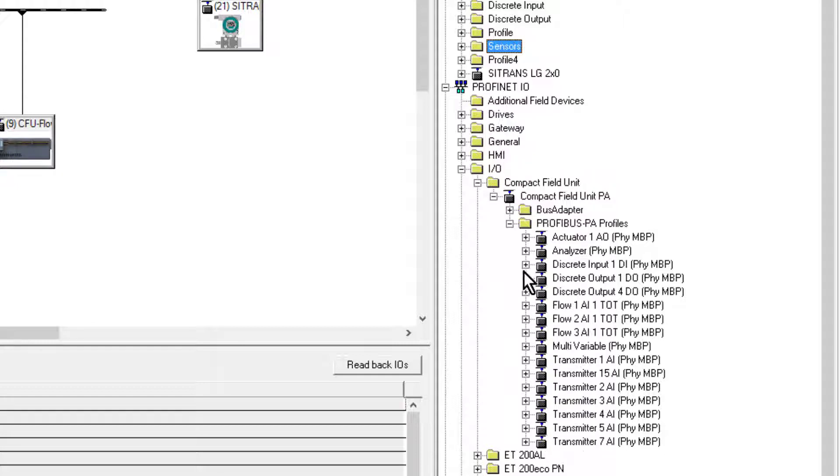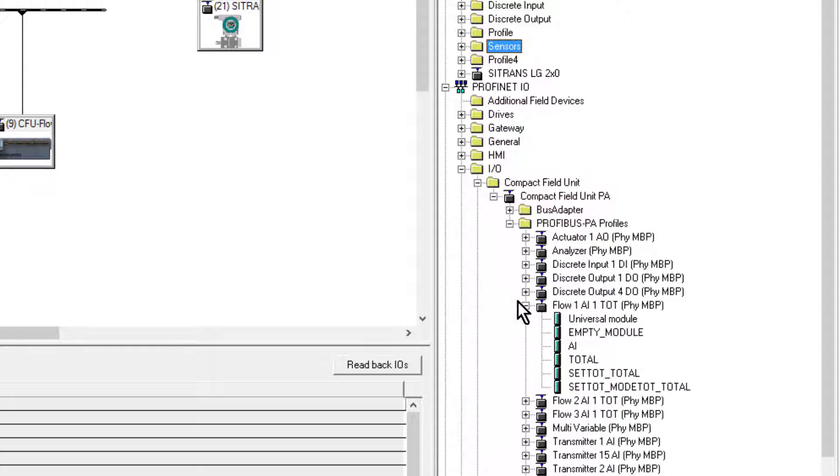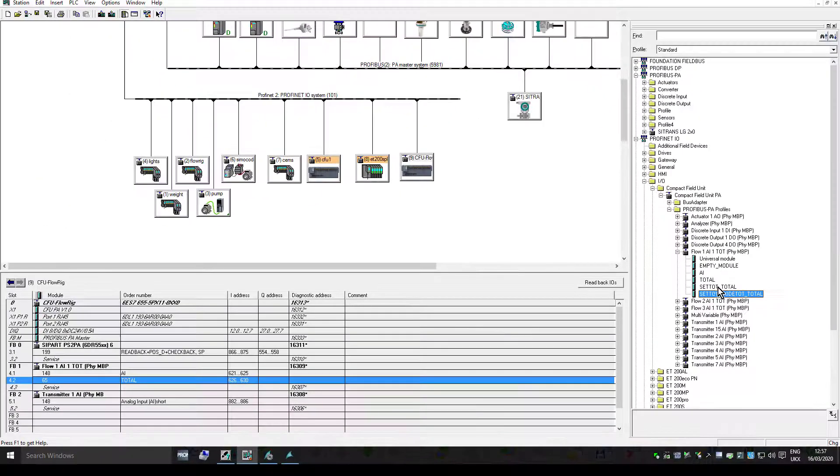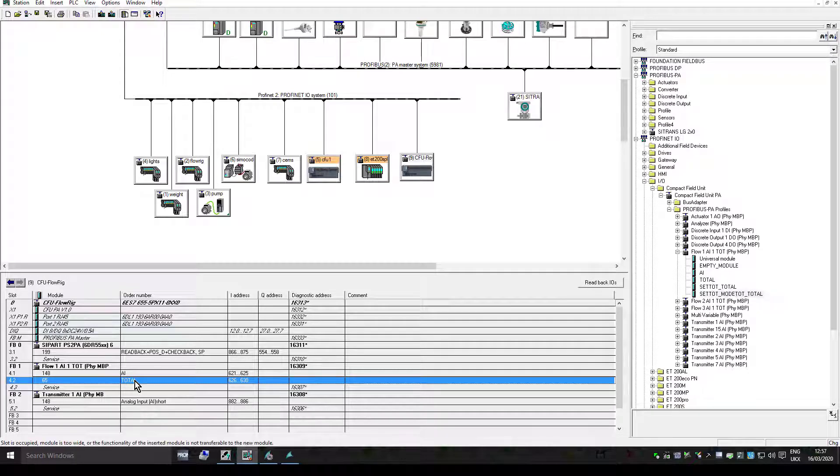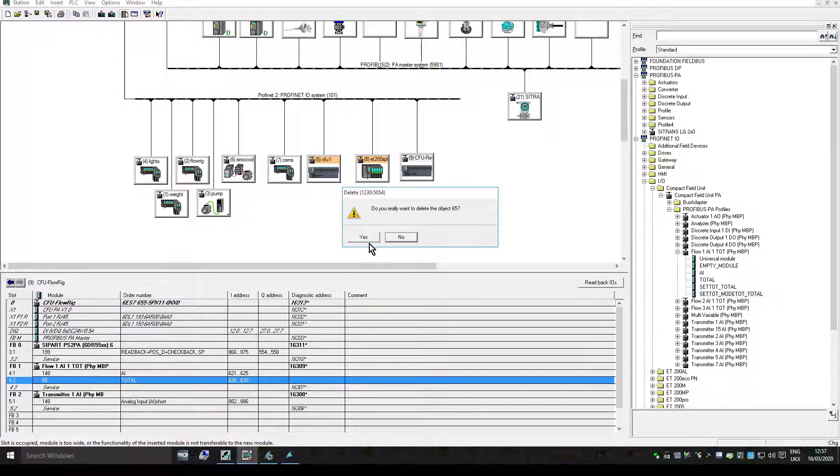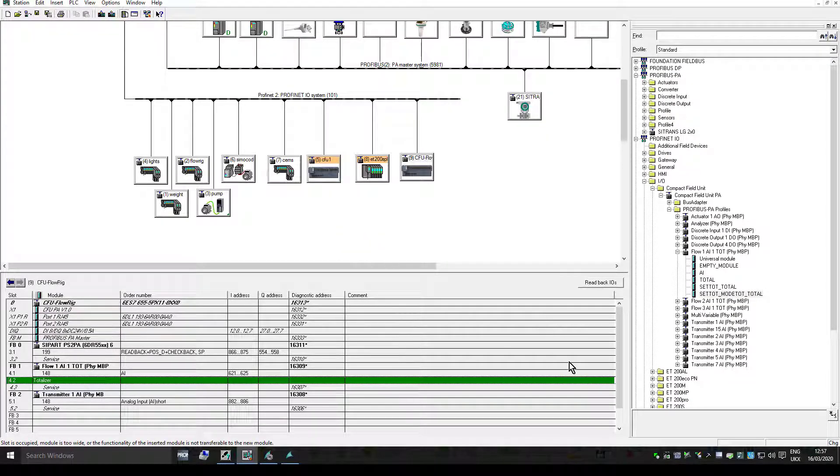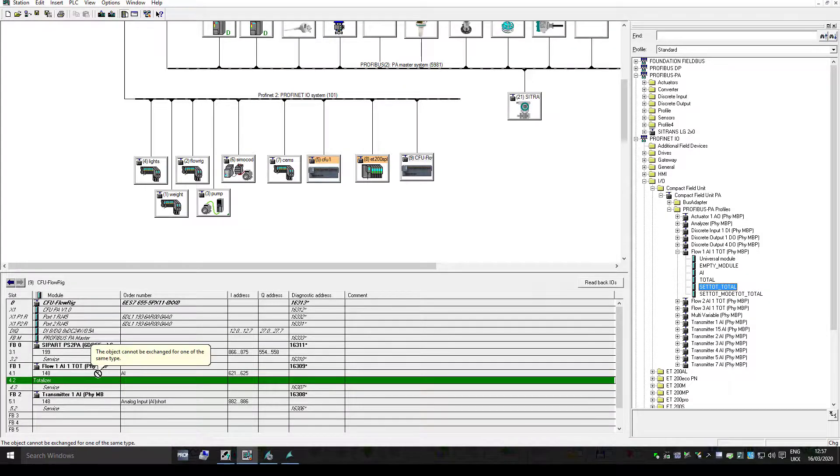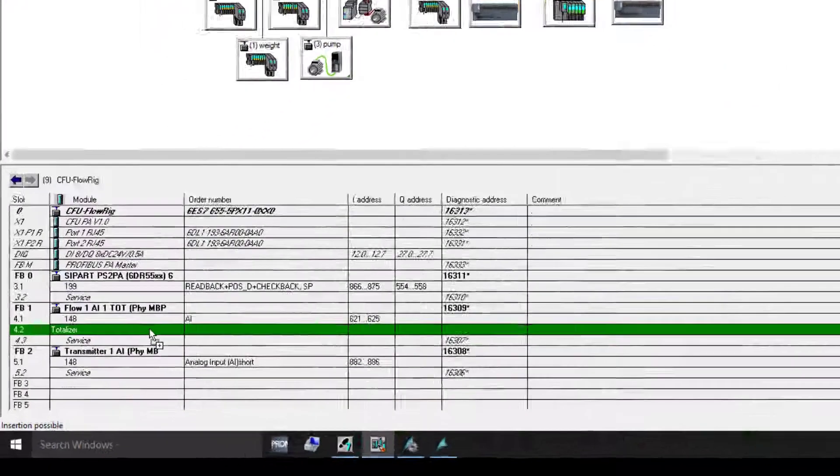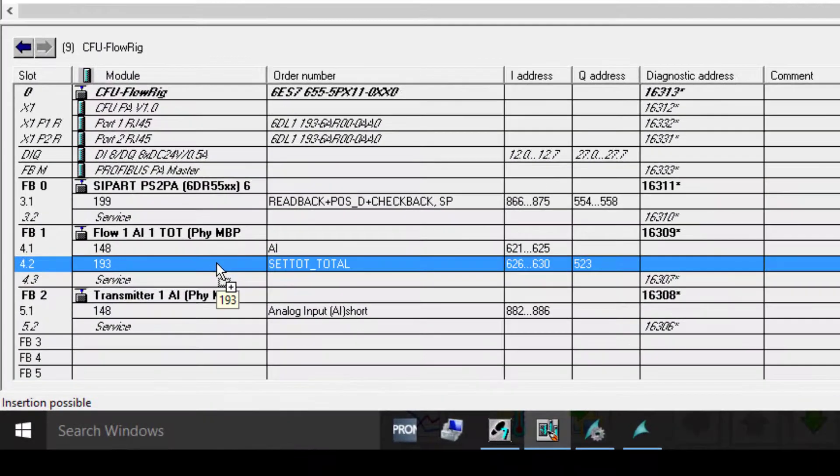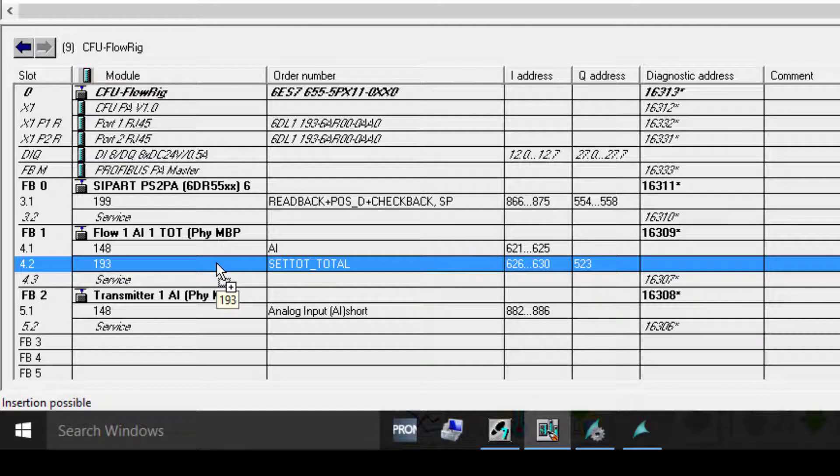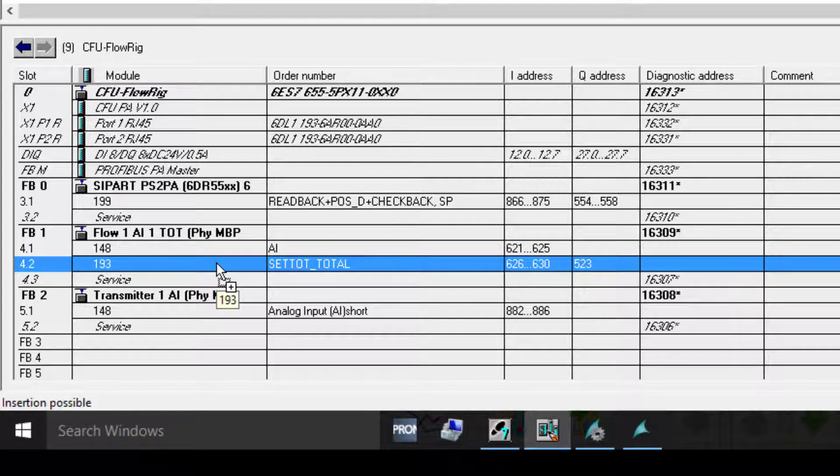I have a look through my list - there's a totalizer. And you can see here that I could delete this totalizer control and upgrade it to one where I can do resets. That is a standard profile-specific function, so you don't have to have the manufacturer's GSD for that.